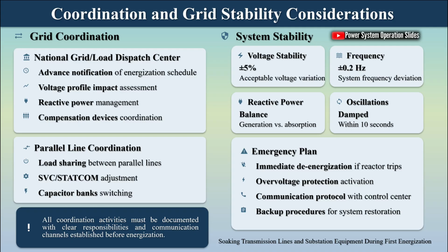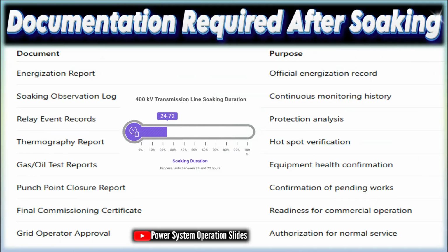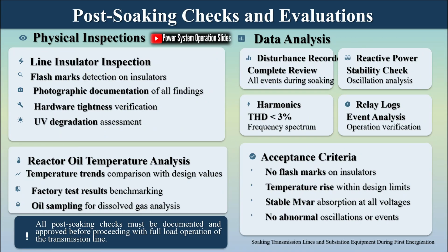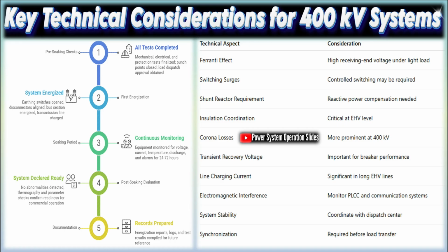Applying full system voltage instantly to new or refurbished equipment can subject insulation systems to sudden electrical forces that may aggravate existing weaknesses. Controlled soaking allows voltage stress to build progressively, giving insulation materials time to adapt to operating conditions. This approach is especially important for high voltage and extra high voltage installations where insulation systems are subjected to extremely high electric field intensities. By reducing the likelihood of sudden dielectric failure, soaking contributes to safer commissioning and greater equipment reliability.